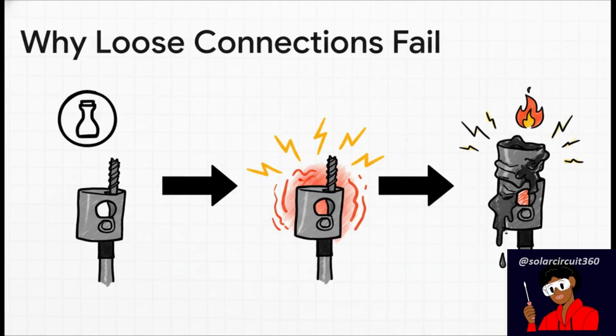So let's connect the dots here. A loose connection creates high resistance, so the R in our formula gets bigger. Then when you turn something on, you're pushing a ton of current, the I, through that tiny high resistance spot. Because that current factor is squared, the heat it generates just skyrockets. We're talking extreme heat, which leads to electrical arcing, melting terminals, and, yep, fire.